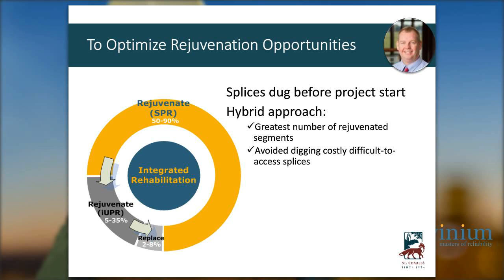I can't overstate enough how the customer experience from cable injection is different from traditional directional boring. As I talked about all the problems in people's backyards, that amplifies when you actually have to send a mini backhoe in there and dig a hole in front of their transformer, then get a directional boring rig into somebody's backyard. You have to dig all kinds of potholes wherever you're crossing some other utility, so it's not just a hole on each end. There's a number of holes in between the two ends of the directional boring span.